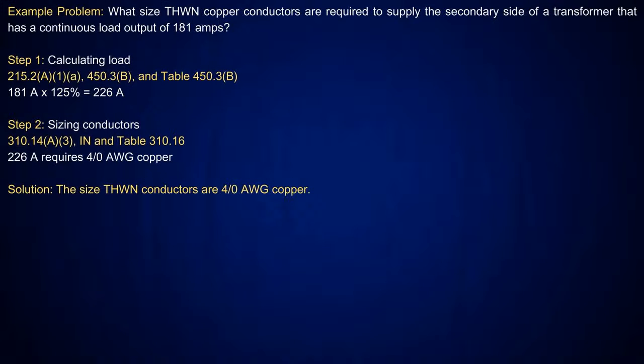All right. Now, this one is where we're going to size the copper conductors that supply the secondary side of a transformer that has a continuous load output of 181 amps. Now, if it is continuous, I have to take it at what?